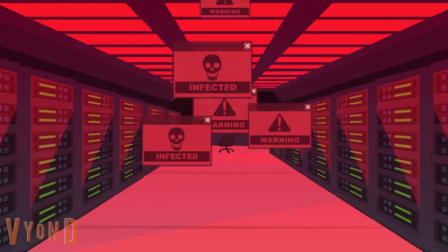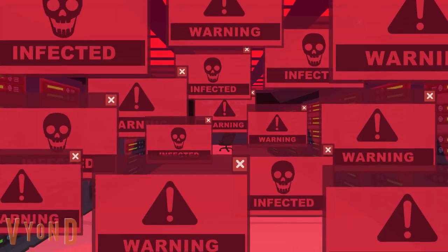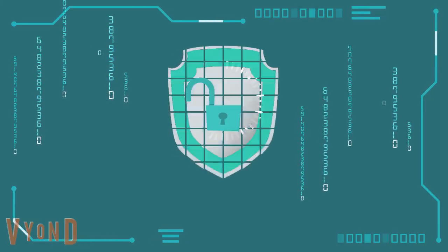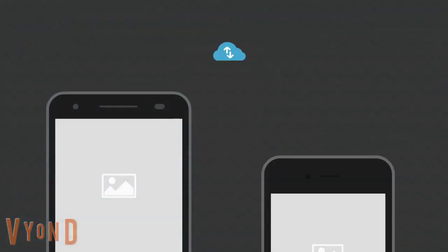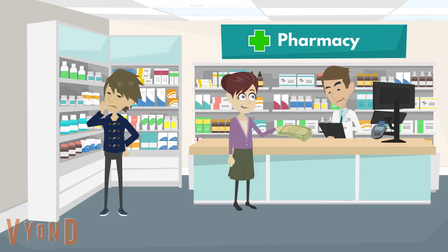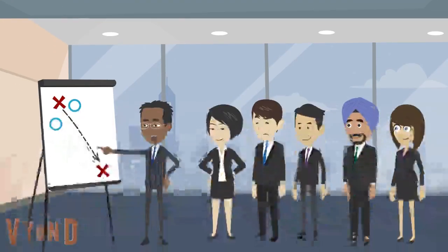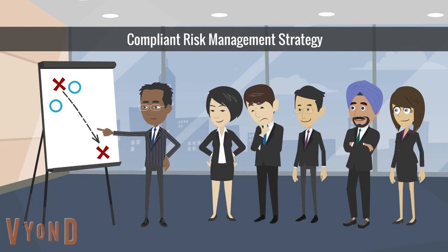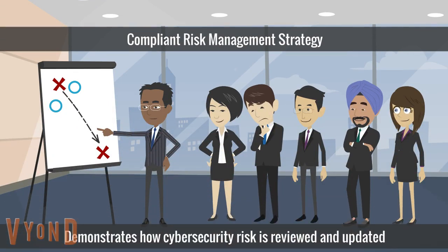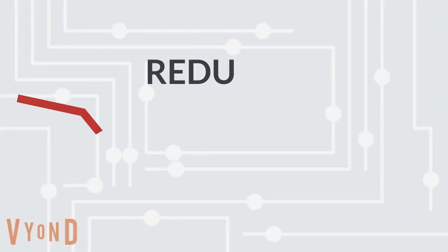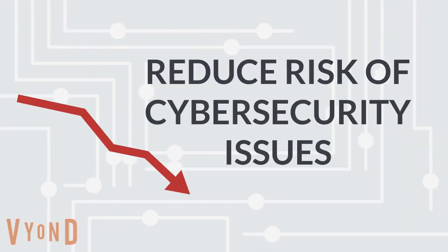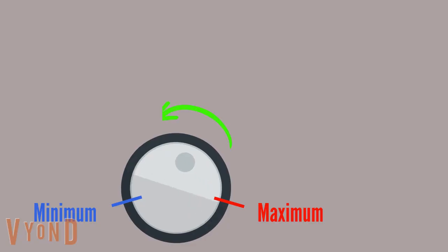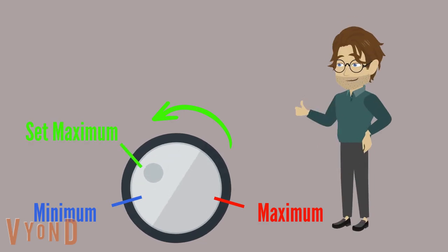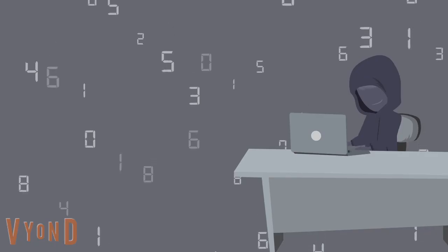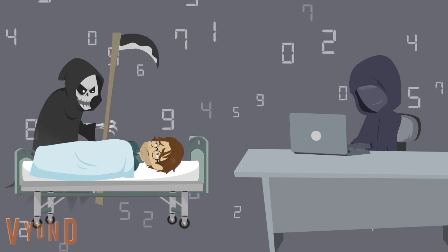Some of the pre-market considerations include cybersecurity penetration testing, operating platform security, and the precautions in the uploading or downloading of data. After the devices hit the market, the manufacturers must have a compliant risk management strategy that demonstrates how the pump's cybersecurity risk is reviewed and updated. To reduce the risk of cybersecurity issues, current-day insulin pumps have the option of setting a maximum dose of a safe amount to ensure that hackers are unable to deliver potentially fatal doses of insulin.